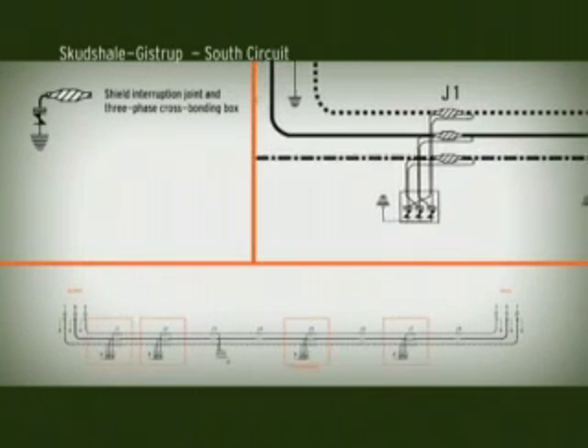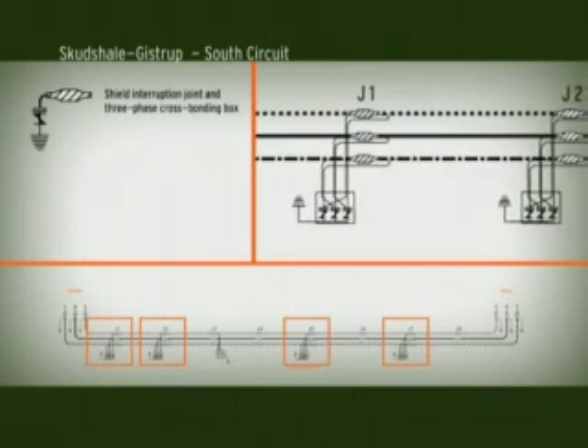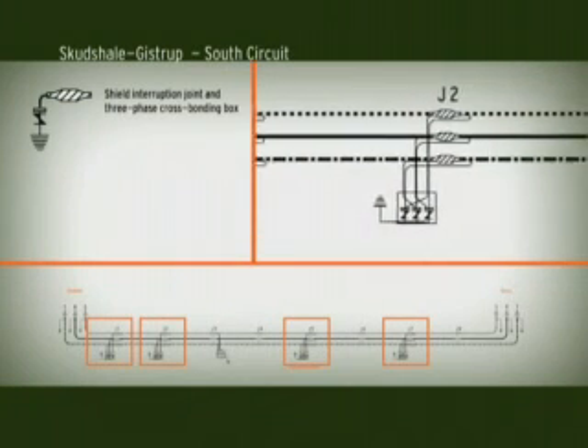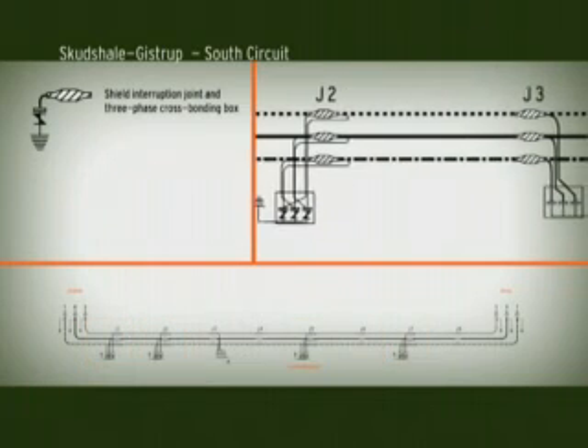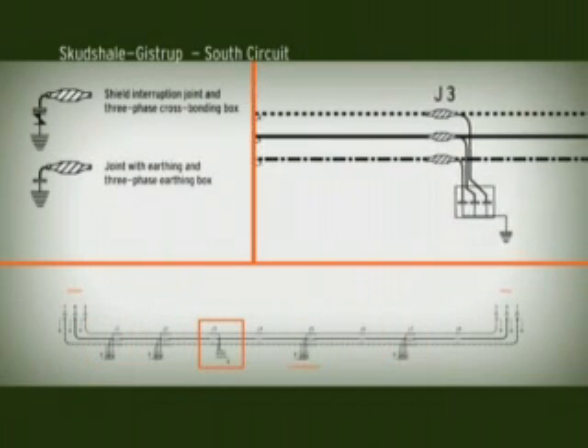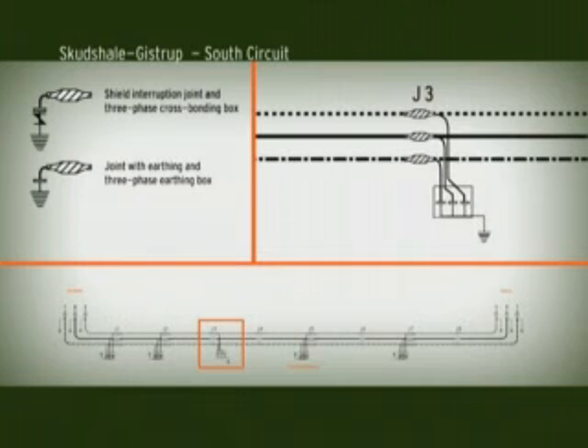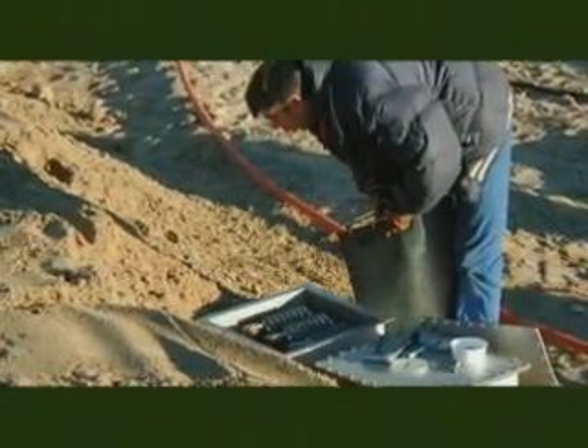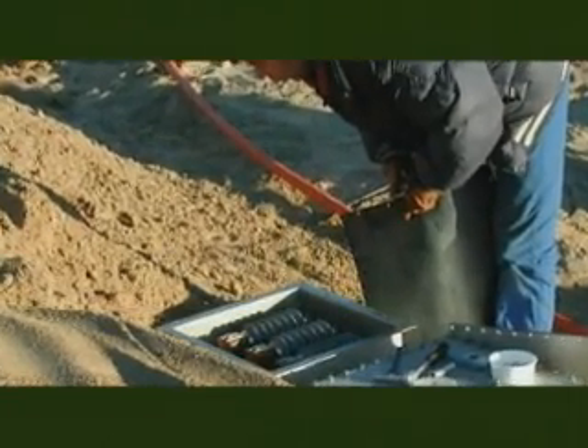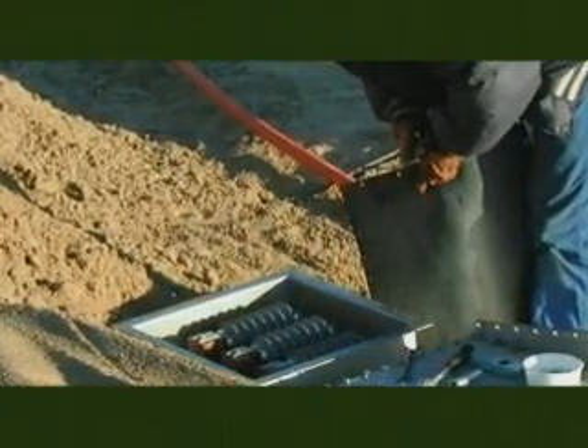The section has 8 joints. Joints numbers 1, 2, 5 and 7 feature shield interruption, with the shields being led out into link boxes where they are crossed. In joint number 3, the shields are led out into link boxes for earthing. The 2 boxes at joint number 3 are placed above ground as a cabinet. This provides access to the bonding. This is necessary for subsequent control measurements of the shield's isolation properties in relation to the earthing. The other link boxes are buried together with the cables. Joints numbers 4, 6 and 8 feature no shield interruption.